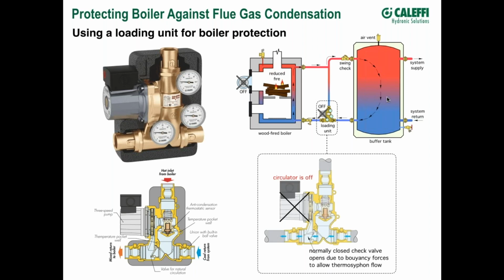With a conventional boiler, that's not a big deal. But with a cordwood gasification boiler, you could have 60 pounds of firewood burning at full rate. Power goes out, and of course the pump is going to stop. So this allows that gravity flow or thermosiphoning, and that's actually what that little gate is for. That little gate would be held shut by the differential pressure of the pump when the pump is operating. And so you can fill through that one too. That was the difference between the drawing he was using. He wasn't using the exact component we showed, but we should make note of that in the future: if you have a check valve in the three-way valve, you might not be able to fill through it.